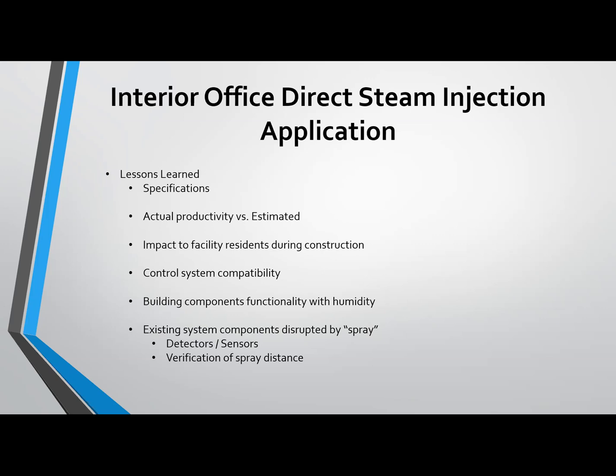Building components functionality with humidity -- this was a very big one. As I mentioned, the facilities were a little small or a little old, and some of those components -- drywall, ceilings, doors -- don't react well to increased moisture in the air. We found that facilities with a lot of metal had some surface rust with increased levels over time, and probably the biggest thing we've seen is swelling of components, especially wood doors -- closing, opening, getting stuck. New facilities, great, you can design that in. Older facilities, you need to look at what you have and what the effects may be. We're getting through it, we fixed a lot of doors, but we're getting there.